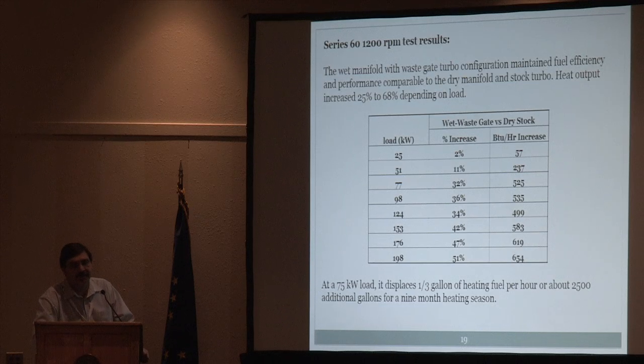Of course, running smaller or slower, it doesn't put out as much heat. So at about a 75 kW load, it'll displace about 1/3 of a gallon of heating fuel per hour, or about 2,500 additional gallons for a 9-month heating season, which can also be very significant at $5 or $6 a gallon for fuel.